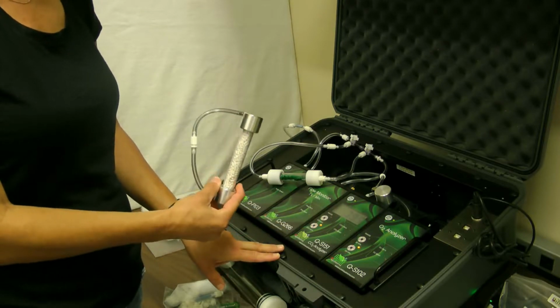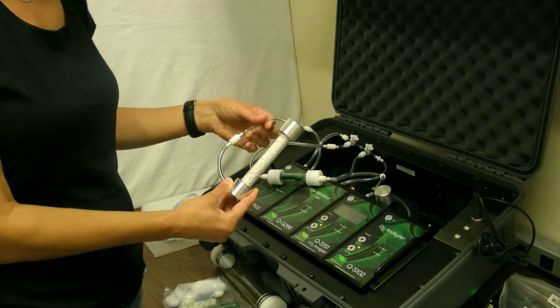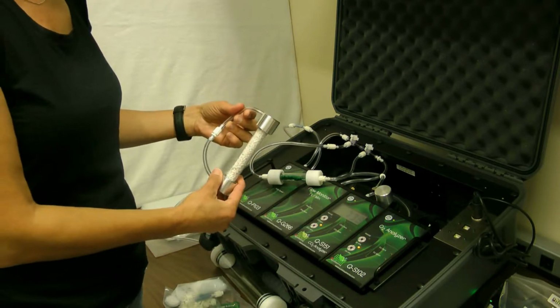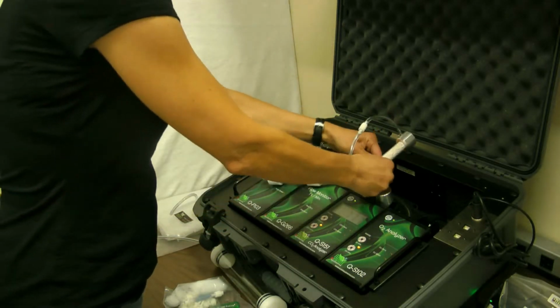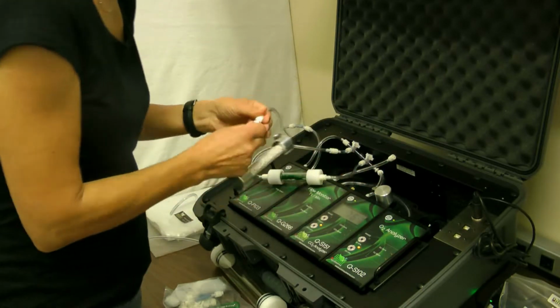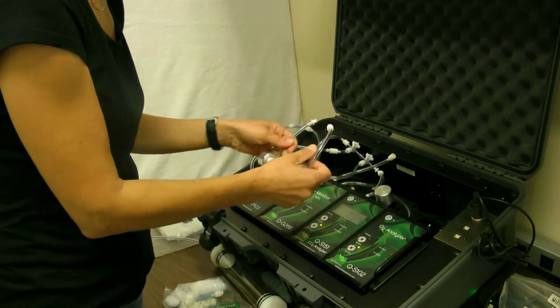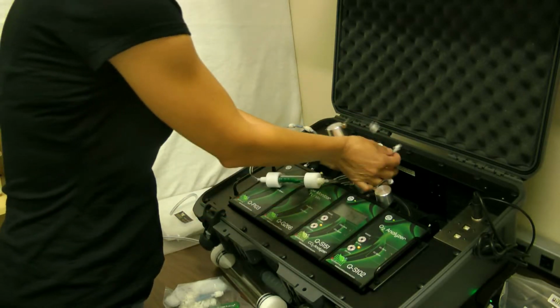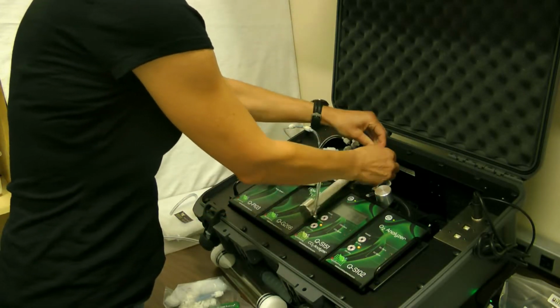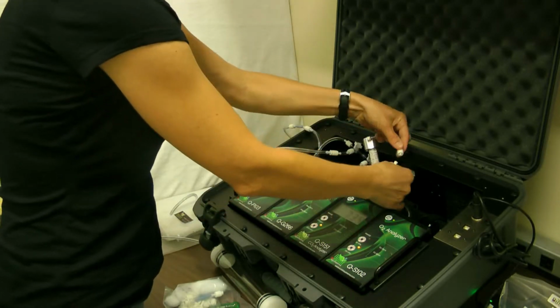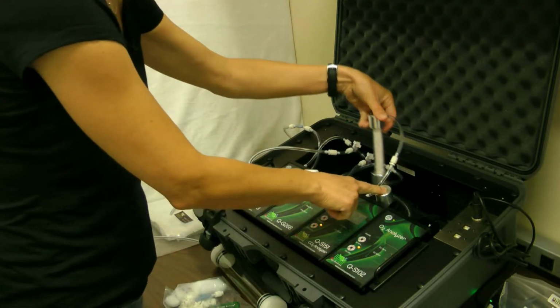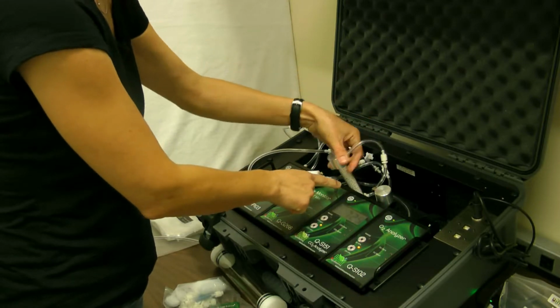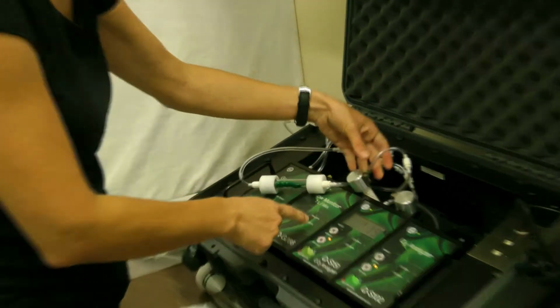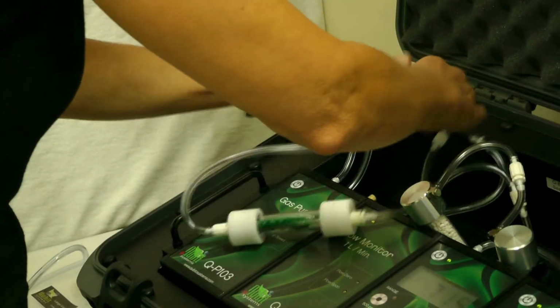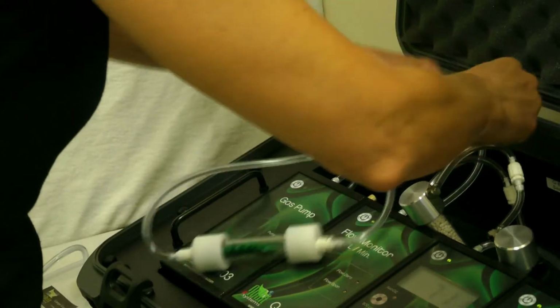One is the 0 CO2, and that can be provided by supplying gas through the soda lime column. And you would do that by placing the soda lime column just in front of the CO2 analyzer. So right after the flow monitor. So you connect it to the flow monitor and then straight to the drying column. Make sure that the soda lime column stays in the upright position. And of course you would detach these 2 valves and your sample from the system for calibrations.